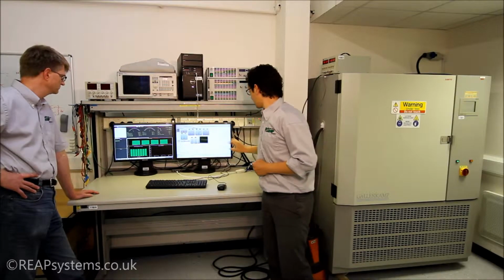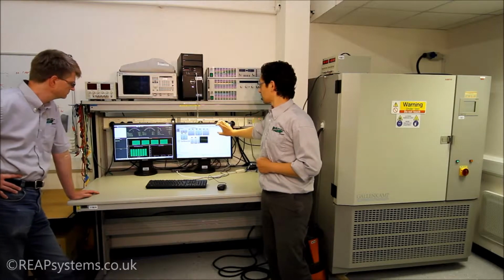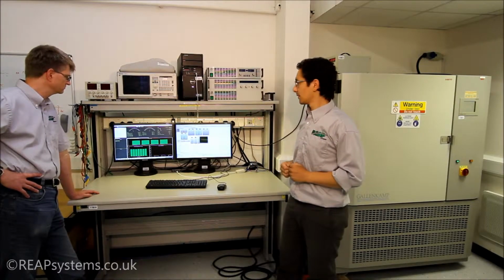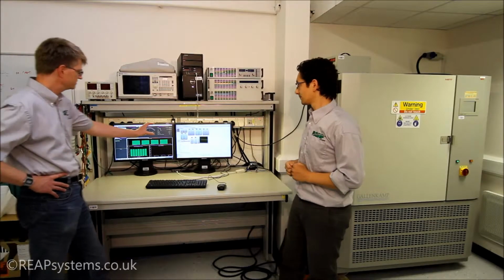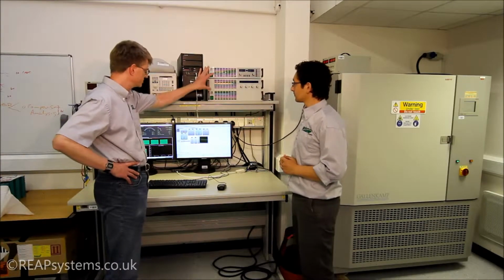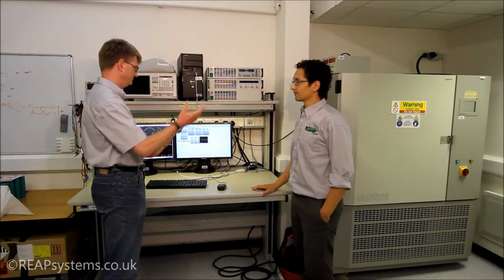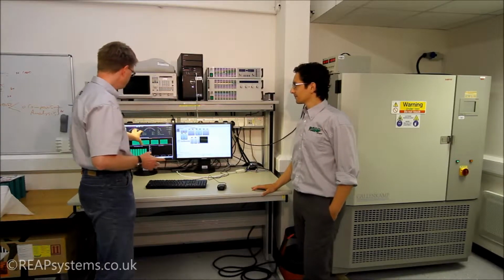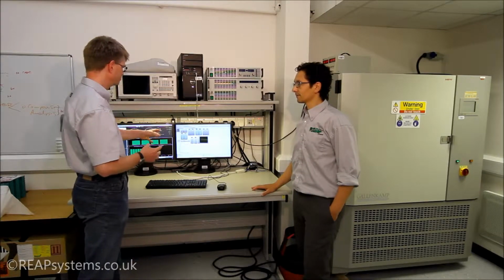But the BMS via the CAN bus is also able to modulate our request to the electronic load and power supply, and reduce it to keep the battery safe, be it for temperature, current or voltage. So this here is telling the electronic load and the charger what to do. That could be either a drive cycle or just a discharge or charge current. We are asking the electronic load or charger to do something to the battery, and then the BMS can interfere with that and make sure the battery is kept safe. That's how it works. Yes.